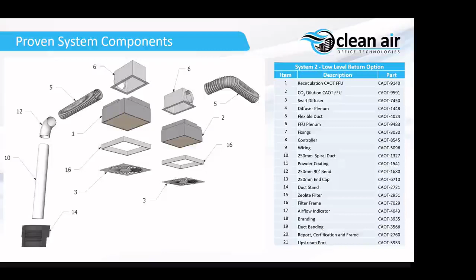Obviously we didn't expect everyone to take our word for it, so we wanted to find out just how well the system performed. Using the space we're in currently, we put in an artificial particulate challenge of about 100,000 particles per cubic metre, then ran a top-of-the-line mobile filtration system. You see the blue trace here - that's the number of particles counted every minute. After about 20 minutes, half an hour, it cleaned down to about 1,600 particles per cubic metre, but after that it couldn't get any lower, which bears out our findings that it wasn't sweeping down the entire room - it was only doing a small proportion of it, circulating at one end, not sweeping down the entire space.